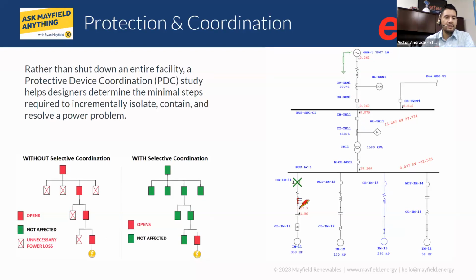And what that means is it's a radial system. So if you go all the way to the bottom, I have a yellow lightning bolt. That is the location where we have a fault. Maybe one of the cables, right, a line touched the ground, or two lines touched. Maybe somebody was working with a tool and it made a line to ground fault. In this case, you notice that there are multiple protective devices that trip.